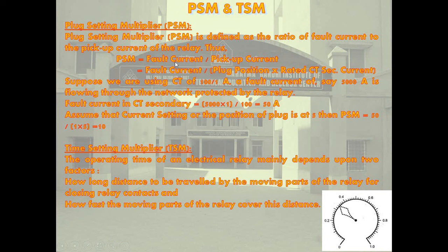Now, the plug setting multiplier and time setting multiplier. Plug setting multiplier is defined as the ratio of the fault current to the pickup current of the relay. Thus PSM equals fault current divided by pickup current. What is pickup current? Pickup current is the plug position into rated CT secondary current. So PSM equals fault current divided by plug position into rated CT secondary current.